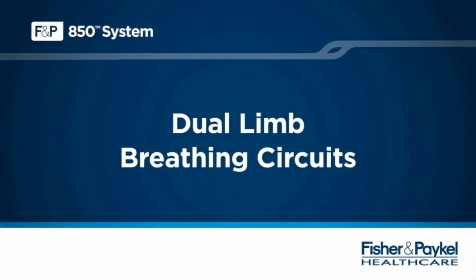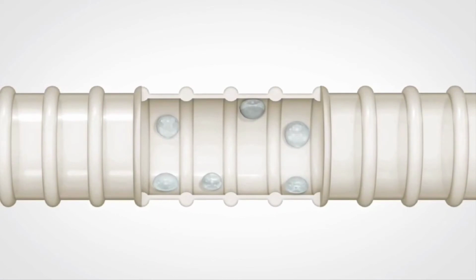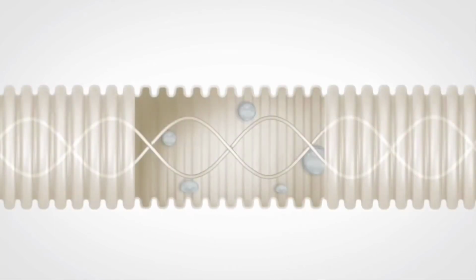Fisher & Paykel Healthcare make a number of different breathing circuits that all manage expiratory condensation differently. Unheated expiratory limbs encourage the formation of condensation that is collected in a water trap and emptied regularly. Heated expiratory limbs minimize condensation by heating the expired gas and keeping it in a water vapor state.